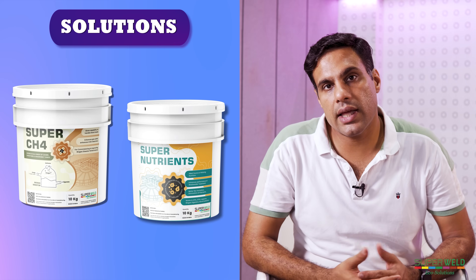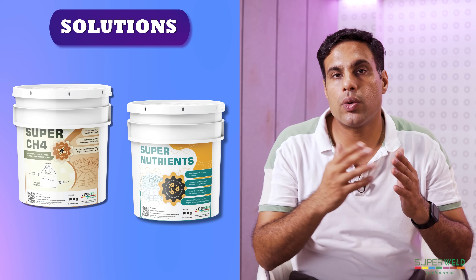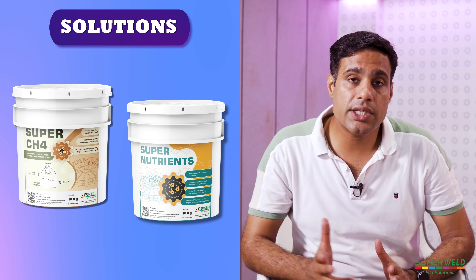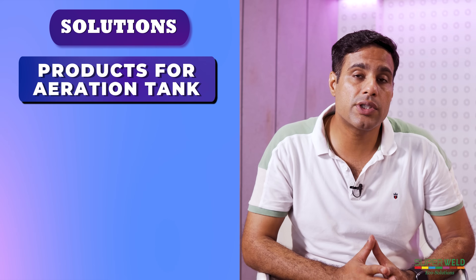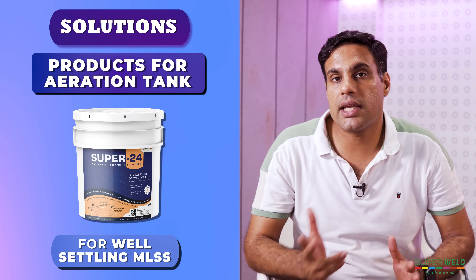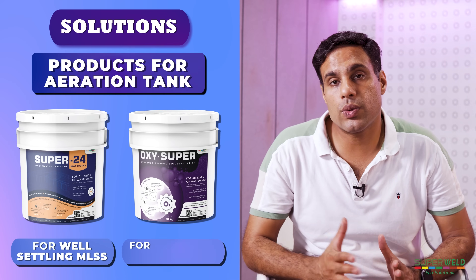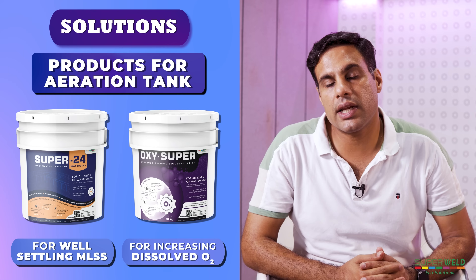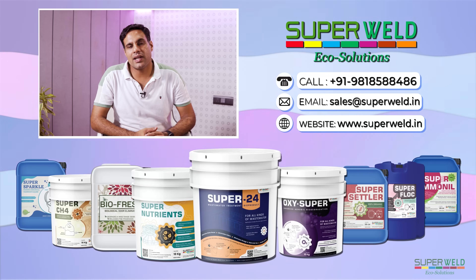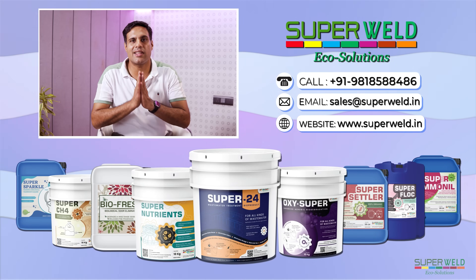When the UASB functions, it can take almost 70 to 80 percent of the BOD load, so that reduced load is transferred to the aeration tank. With a lower incoming load, you can easily set up the aeration and get good results. There are two major products for the aeration tank: Super 24, which gives a well-settling biomass, and Oxy Super, which helps increase dissolved oxygen and gives very clear water quality. If you are facing similar issues, do write to us — we'll be very happy to solve it for you. Wishing you all the best. Thank you and Jai Hind.